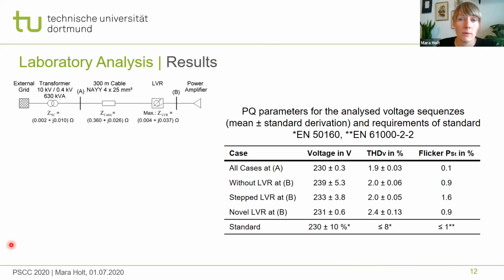This slide gives the power quality parameters for the analyzed voltage sequences. The power quality parameters at busbar A are not influenced by the line voltage regulator as the voltage interferences expand primarily to the subordinated feeder section via the grid impedance. The stepped line voltage regulator decreases the mean voltage at busbar B to 233 volts, which is 6 volt less than at the reference case without voltage regulation. However, the stepped voltage regulation emits flicker. For this scenario, the flicker even exceeds the requirements. In contrast, the novel line voltage regulator reduces the mean voltage to 231 volt with lower standard deviation. Additionally, there is no flicker emission due to the continuous voltage control, and also the output voltage distortion increases just slightly due to the optimized combined control.